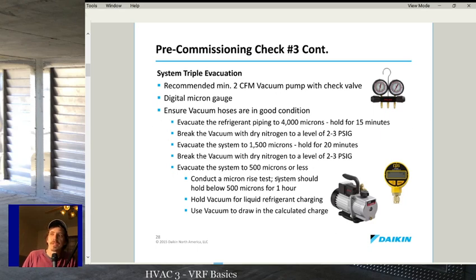And then this is the instruction for a triple vac. If you're having trouble vacuuming down a system, like it's a bigger system, or it's been open for service, a triple evac does end up being faster a lot of the time. I'm serious. I know it seems counterintuitive to break that vacuum with nitrogen and then start vacuuming again, but if you do it a few times, you will find that a triple evacuation will actually save you time in the long run if you're dealing with a system that's been open for service or has some moisture contamination from just being open for too long or something. Ideally, it's closed off all the time, but sometimes that doesn't happen.